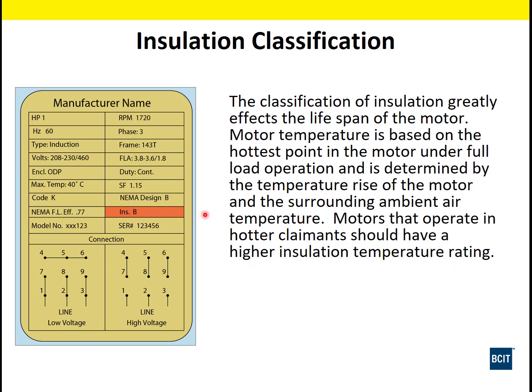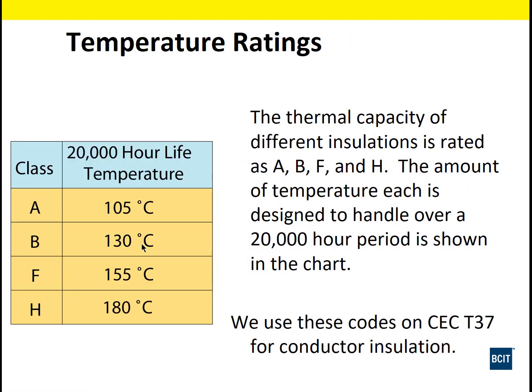Insulation class. This is the rating at which the insulation in the motor windings can operate, with higher insulation temperature ratings. So this table here shows the temperatures they can get up to and operate at. So if we have a type A motor, it can get up to 105 degrees Celsius. Okay, type B 130 degrees, and all the way up to type H 180 degrees Celsius. So that motor can get really, really hot, work under really hot conditions. Now, in the Canadian Electrical Code, we use table 37 to utilize these codes for conductor insulation and conductor to help size conductors feeding these motors.